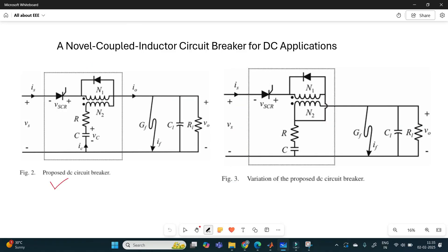Here, figure 2 is our proposed DC circuit breaker. During steady state operation, current flows from the source to the load through the SCR and this coupled inductor. A fault on the load side will cause an impulse current IC in the short path containing the capacitor and secondary winding of the coupled inductor. With the turns ratio, the current is reflected to the primary and essentially pushes the SCR current to 0. At that time, SCR switches off.